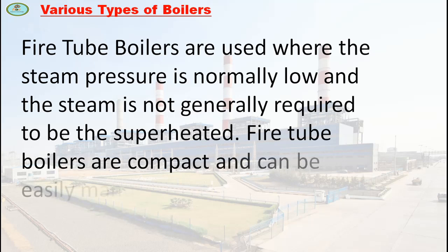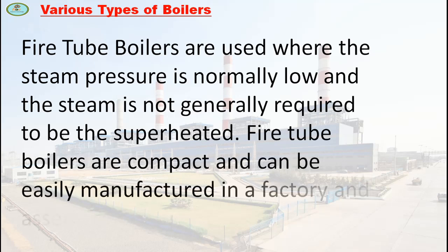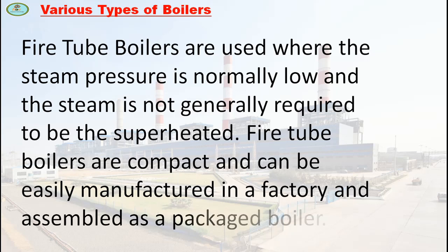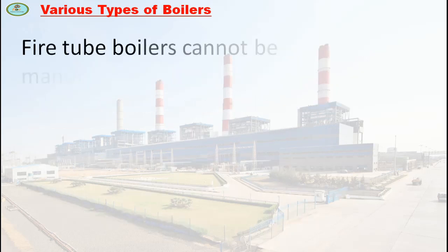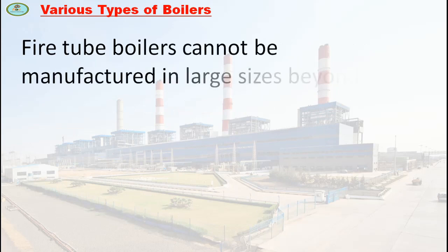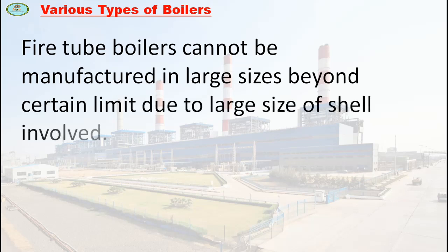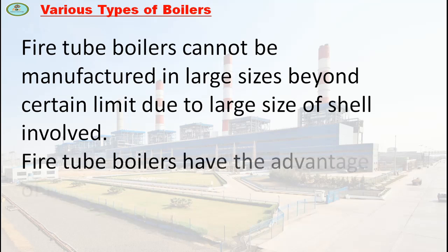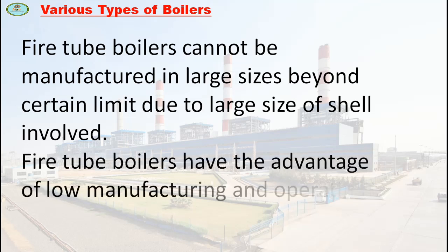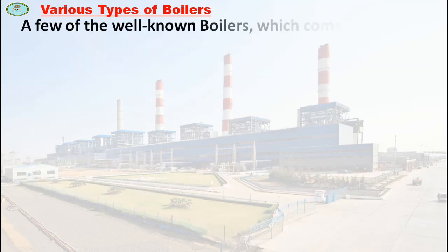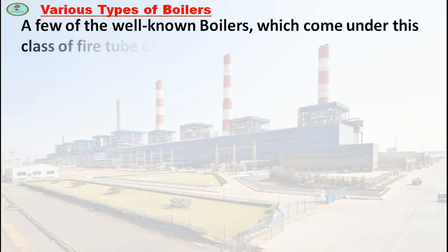Fire tube boilers are compact and can be easily manufactured in a factory and assembled as a package boiler. Fire tube boilers cannot be manufactured in large size beyond a certain limit due to the large size of shell involved. Fire tube boilers have the advantage of low manufacturing and operating cost.